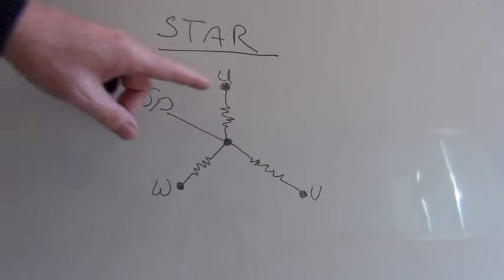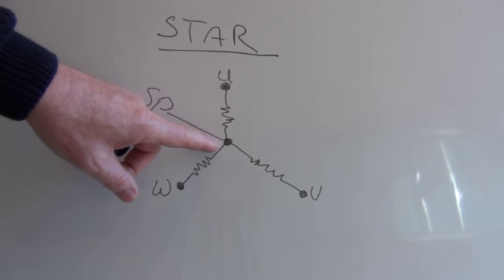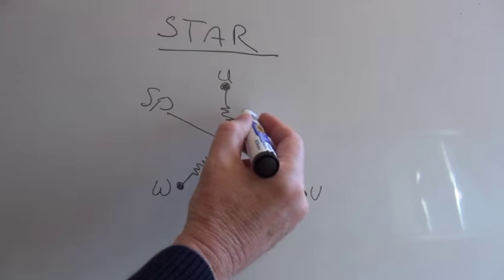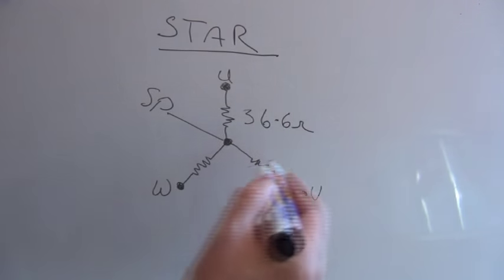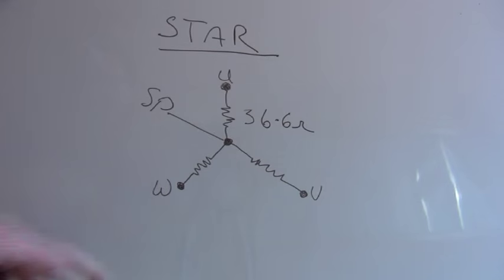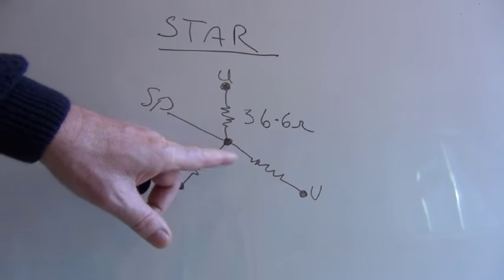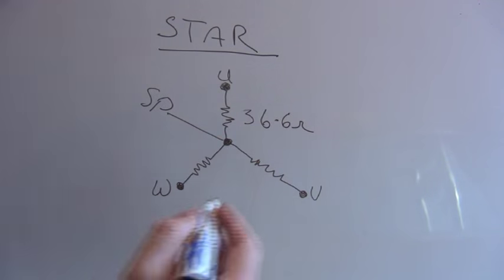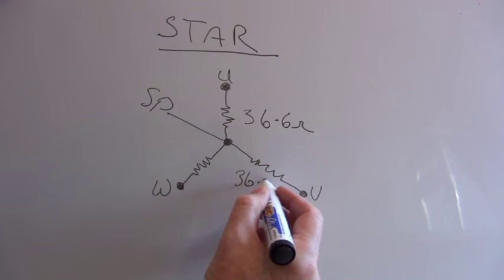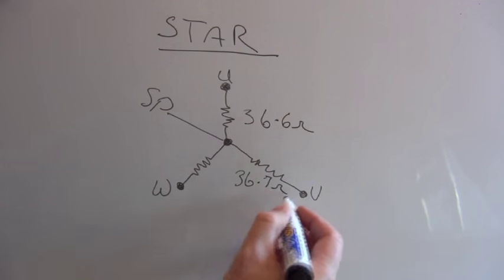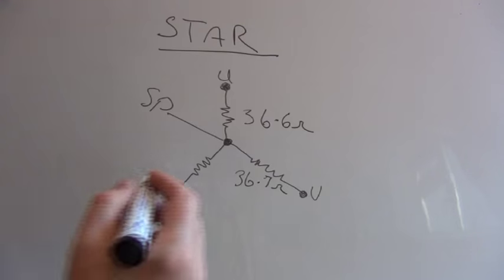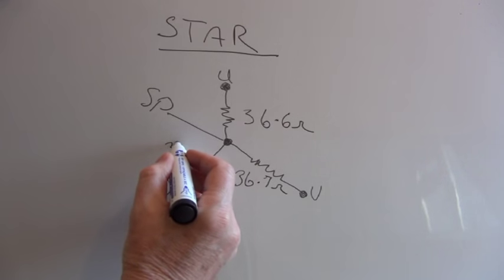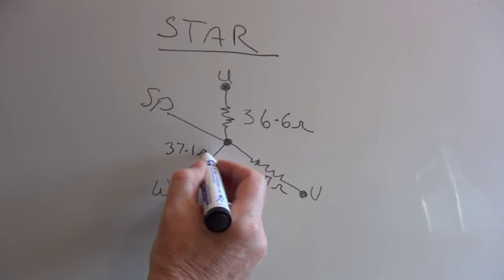The first reading we took was between U and the star point, and we obtained 36.6 ohms. The next reading we took was between V and the star point, and we obtained 36.7 ohms. The next reading we took was between W and the star point, and we obtained 37.1 ohms.